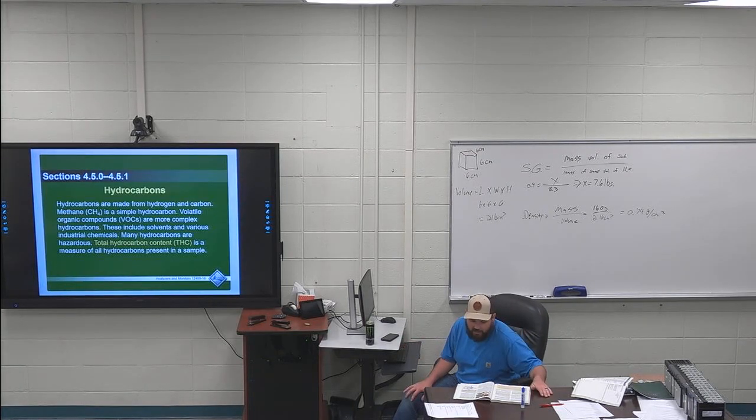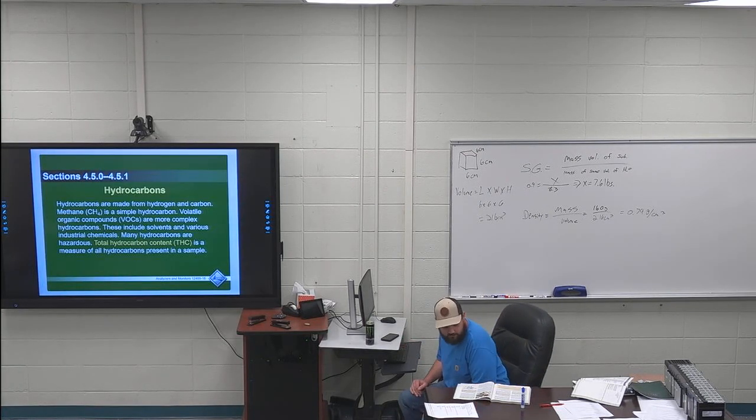450, measuring hydrocarbons. Top right of page 35, first 2 sentences are highlighted. Hydrocarbons, compounds composed of hydrogen and carbon, are present in many forms in atmospheric air. Among these substances is methane, with a concentration of approximately 1.7 parts per million, which accounts for the majority of the concentration of hydrocarbons.